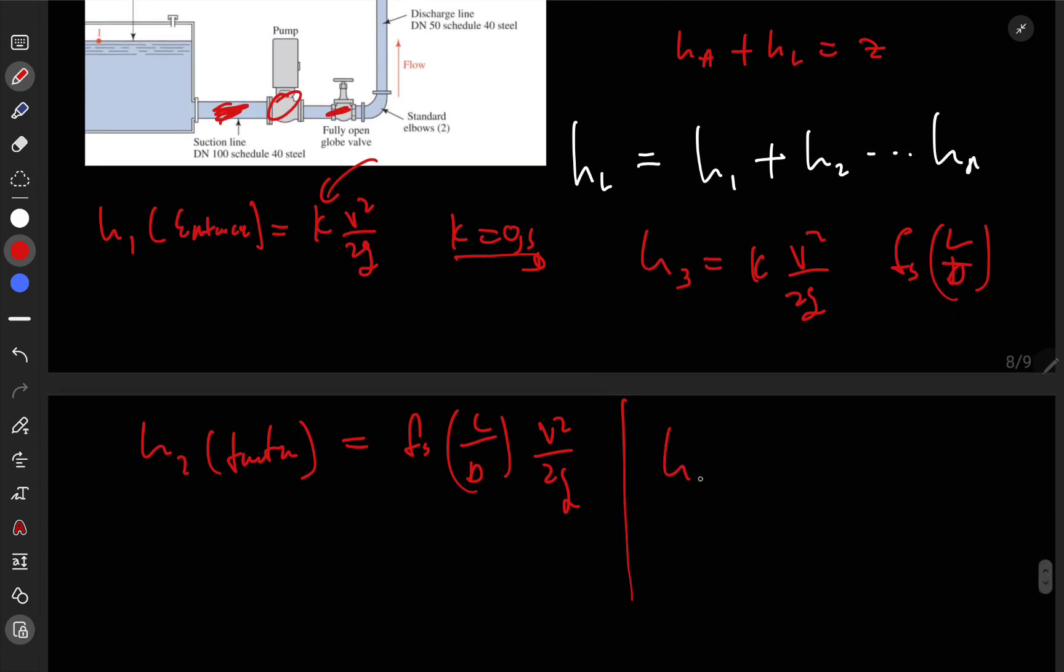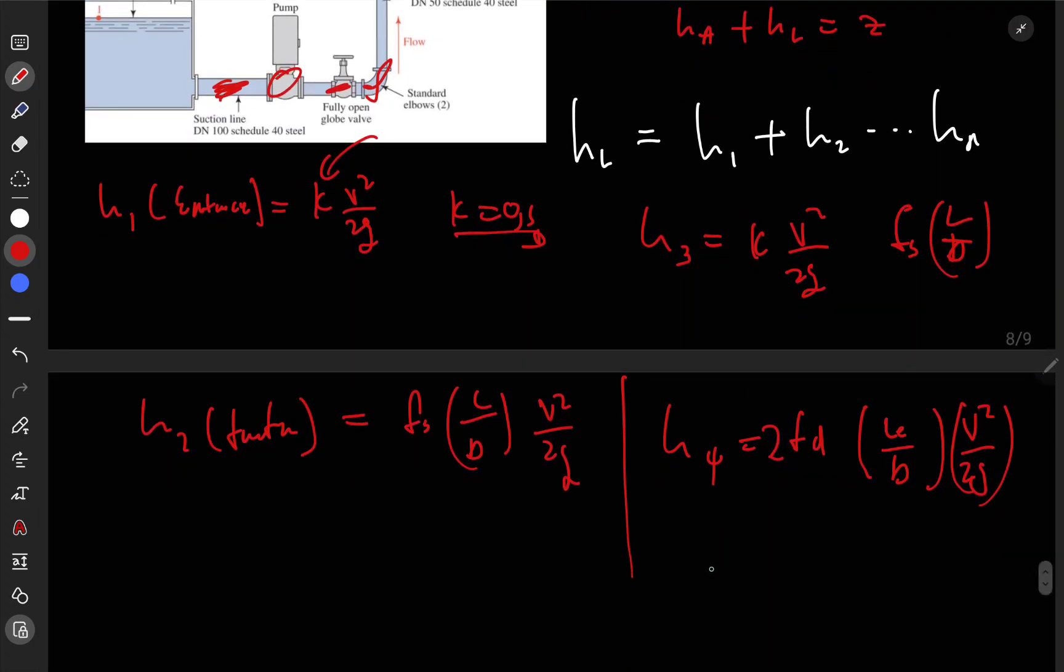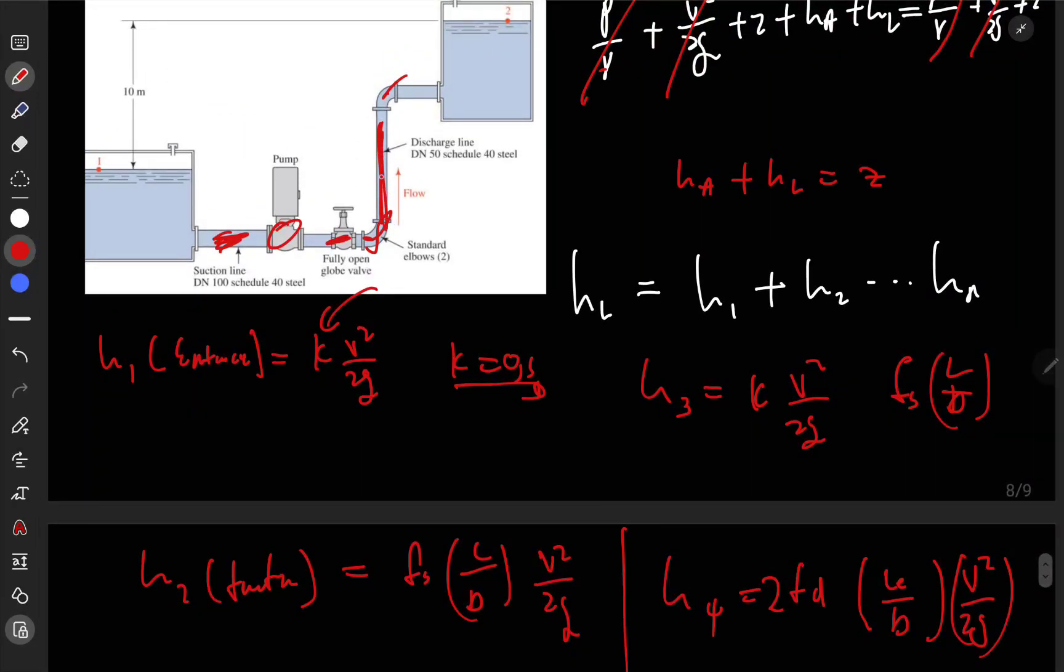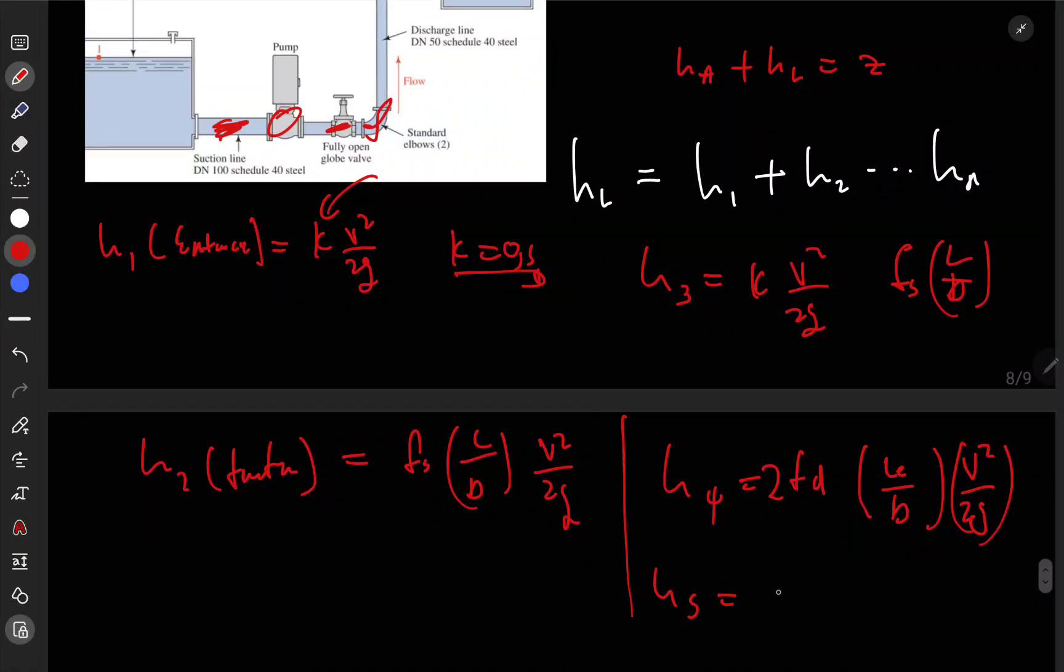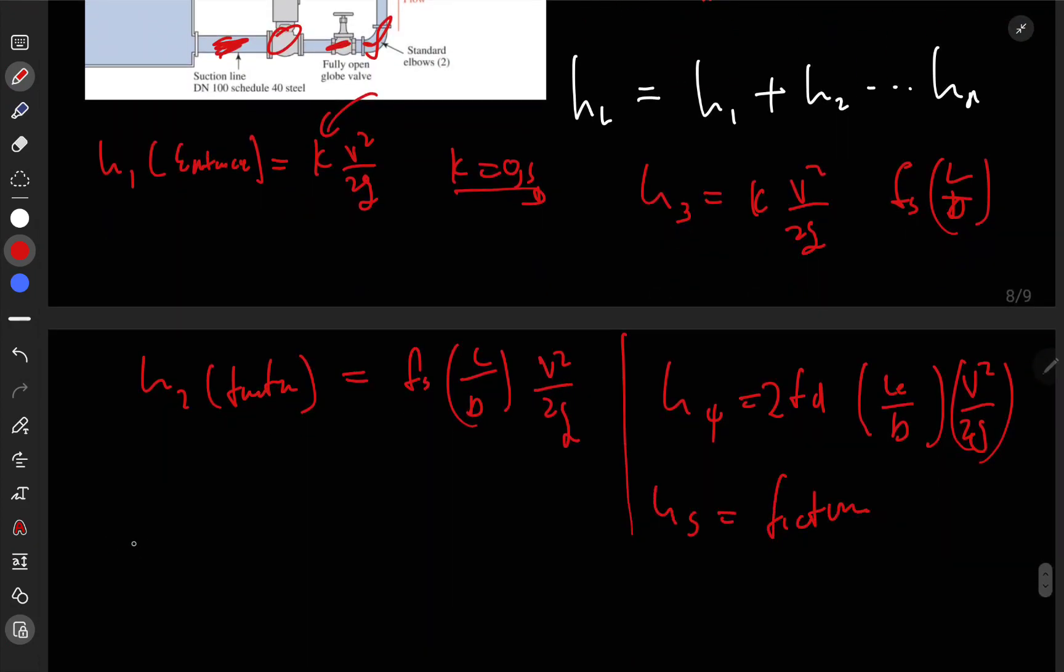Now we arrive here. Here the K for this one is going to be friction factor times L over D, and this one is the equivalent length. Now we are on the elbow. The elbow again is going to be energy loss 4, which equals f_D times L_e over D times V squared over 2g. These elbows are two, so you can do yourself a favor and times it by 2.